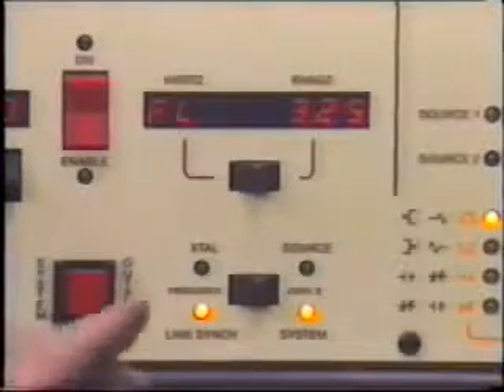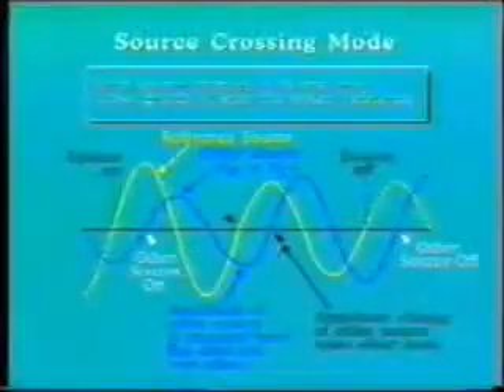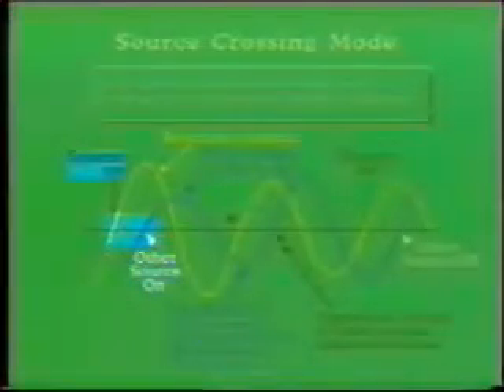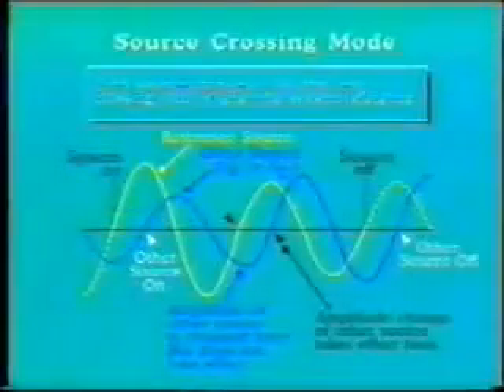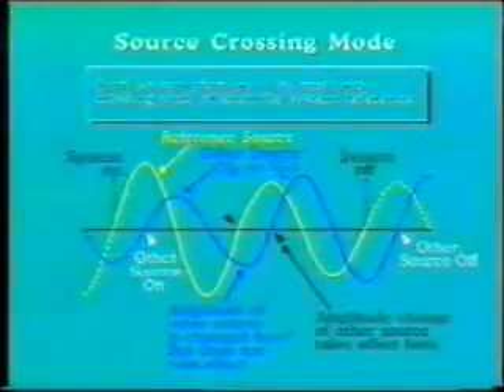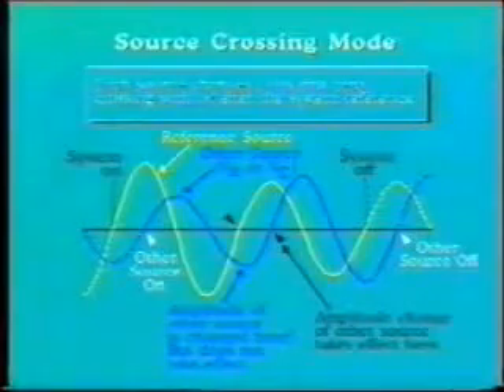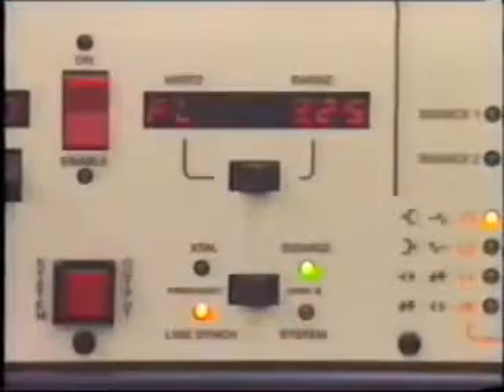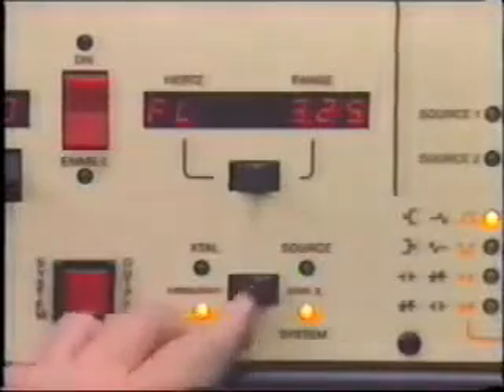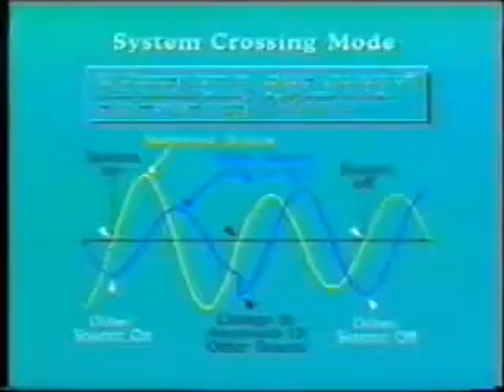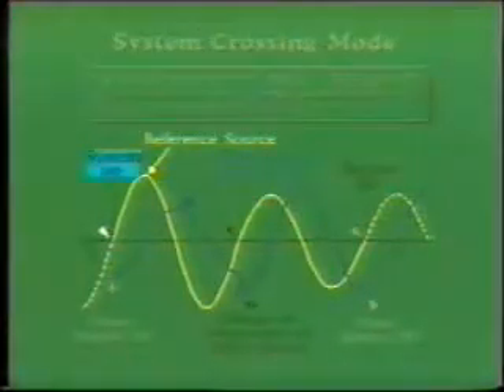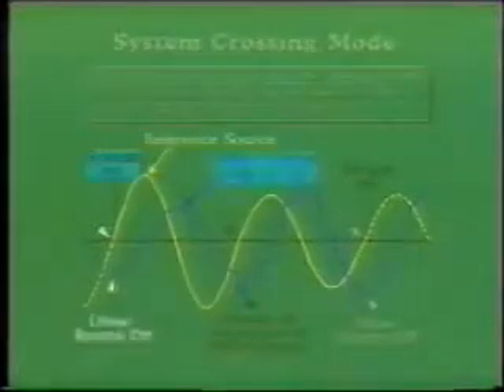The precise point at which each output is energized depends on the setting of this selector switch. Flipping the switch to the right selects source crossing. This means that each output will turn on as its sine wave is just crossing 0 in the positive direction. This works fine for electromechanical relays where a turn-on time difference of 120 degrees is not noticeable. However, with multi-phase solid-state relays, we should select the system crossing mode. Here, the reference source, such as VA, comes on at its positive going 0 crossing. But in addition to this, the other sources, VB and VC, come on at precisely the same instant.